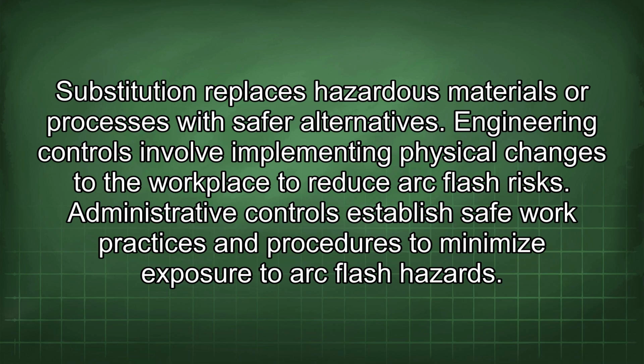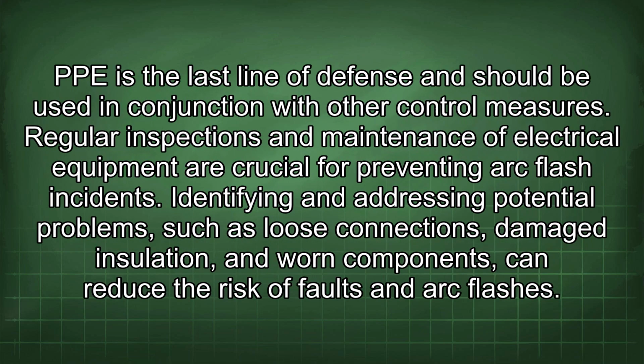Administrative controls establish safe work practices and procedures to minimize exposure to arc flash hazards. PPE is the last line of defense and should be used in conjunction with other control measures. Regular inspections and maintenance of electrical equipment are crucial for preventing arc flash incidents.